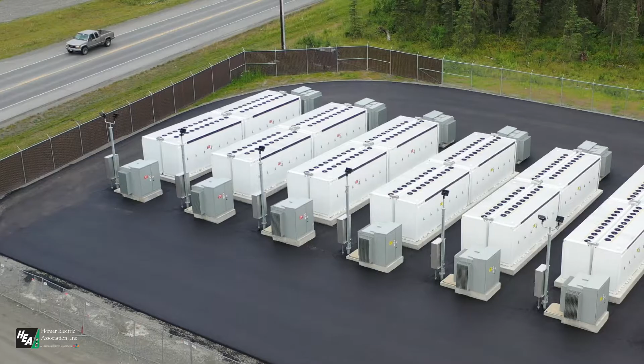HEA's BESS includes 37 Tesla Megapack battery units, weighing in at 52,000 pounds each. The BESS can store up to 93 megawatt hours of energy, and can deliver this at a rate of 46.5 megawatts per hour directly to HEA's 115 kV grid. Tesla's Megapack, introduced in 2019, was specifically designed for large-scale storage to better meet the needs of utilities.